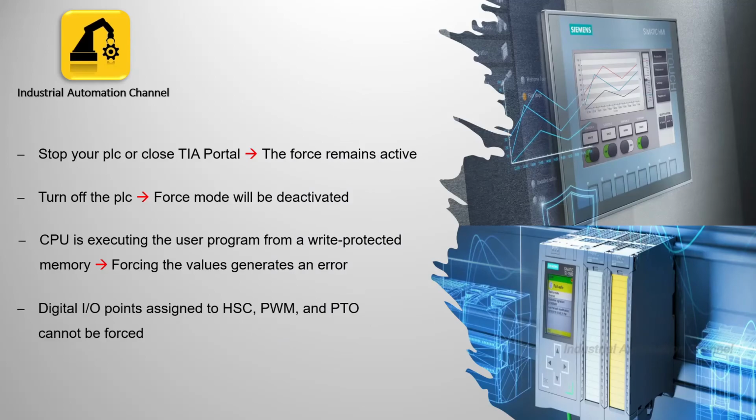The digital input output points used by the high speed counter, pulse width modulation and pulse train output devices are assigned during device configuration. When digital input output point addresses are assigned to these devices, the values of the assigned I/O points addresses cannot be modified by the force function of the force table.